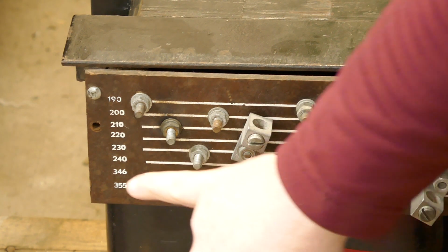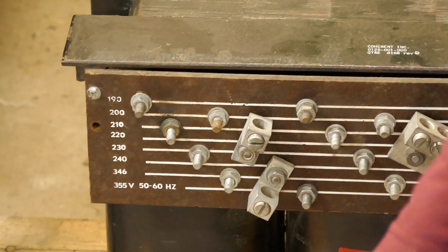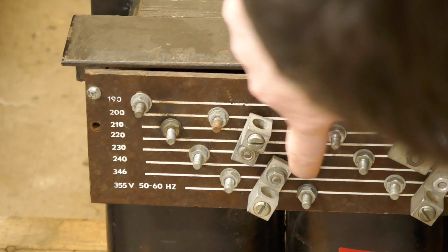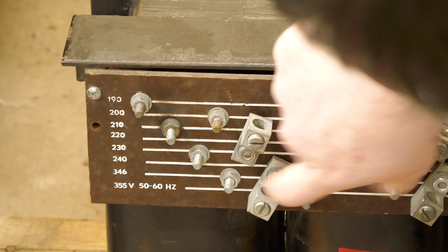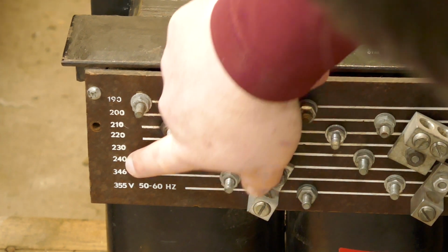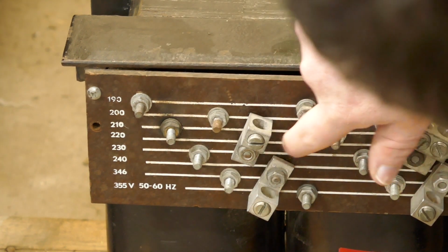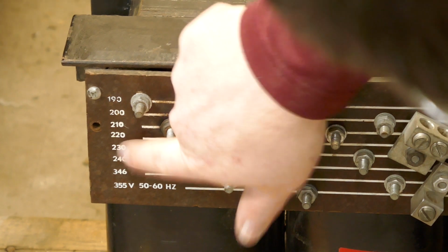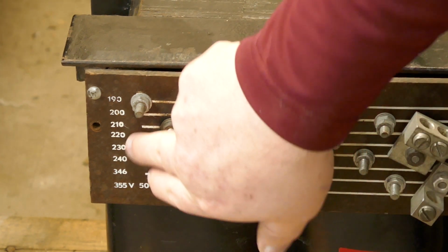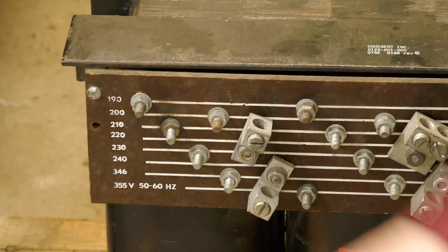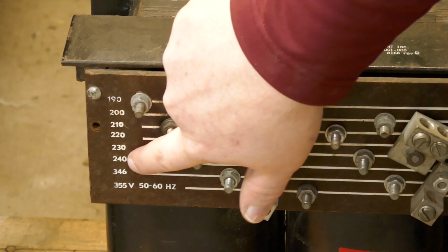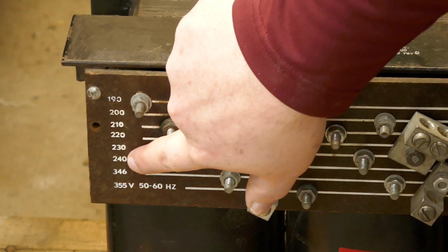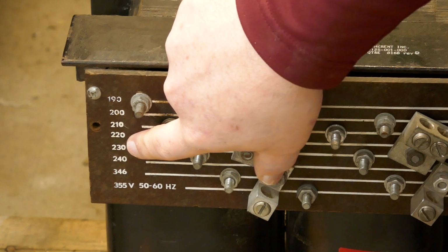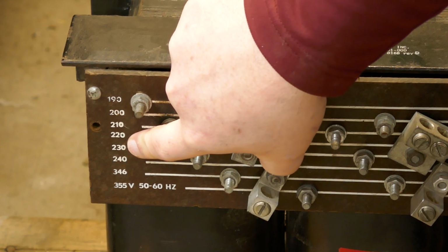But in this case, what I'm going to do is, you've got these lines right here, and one set of lines is on 240, and the other set of lines is on 230. So this is only a 10 volt step down, but if I have 250 volts coming in on the 240, I'll end up getting about 240 volts out.